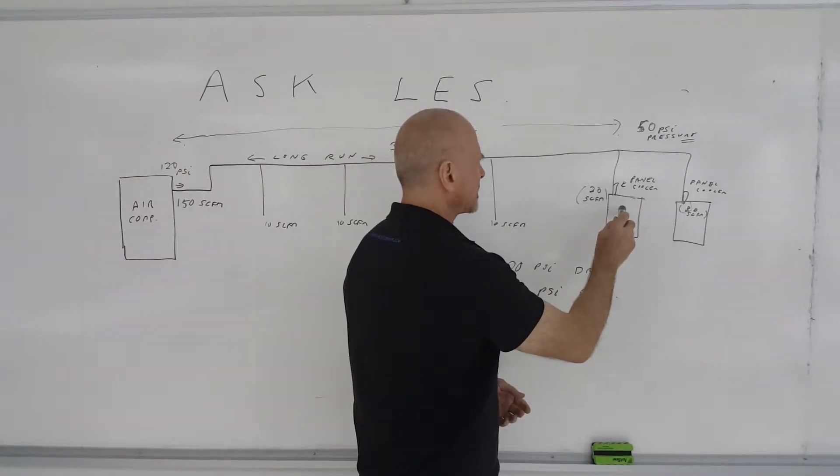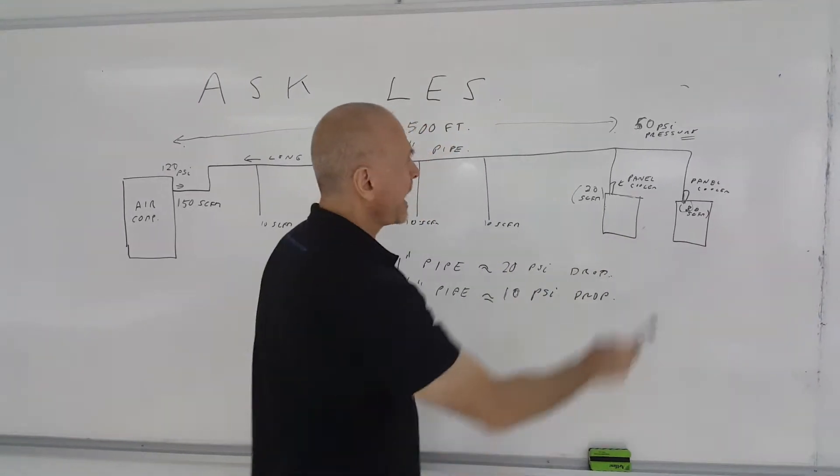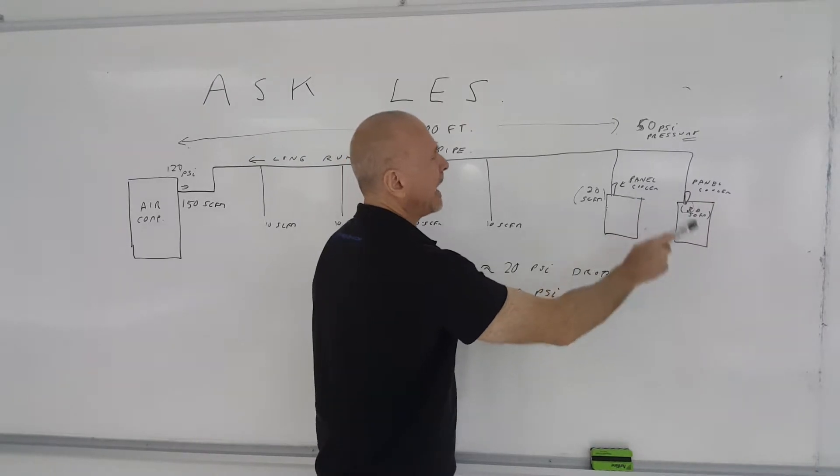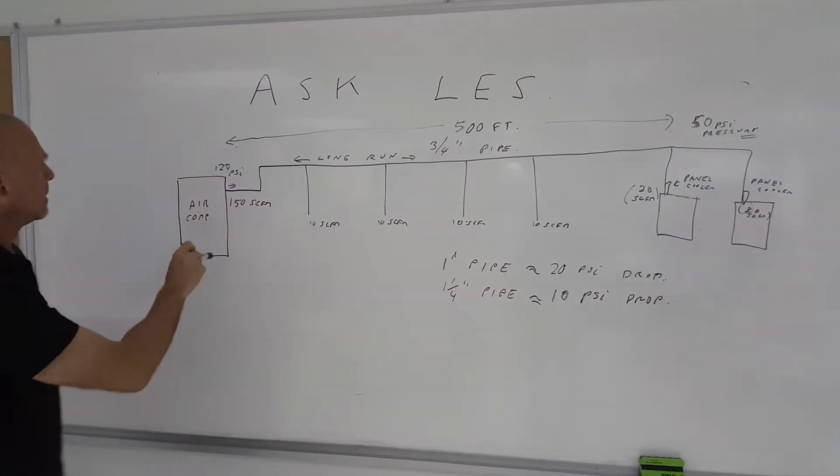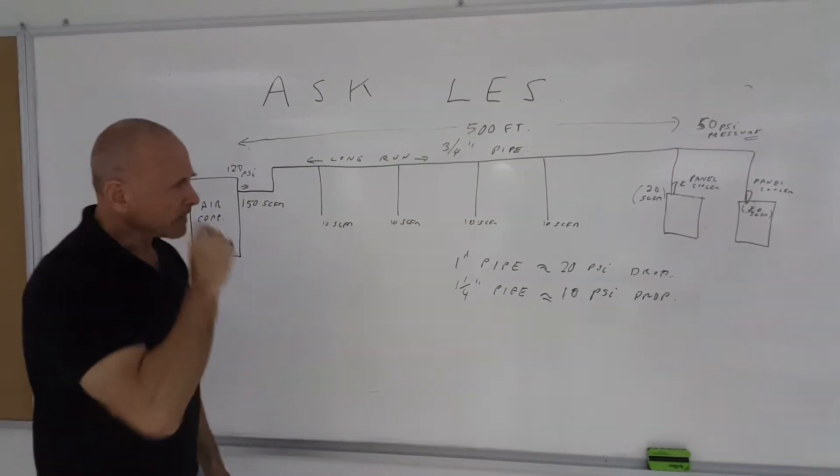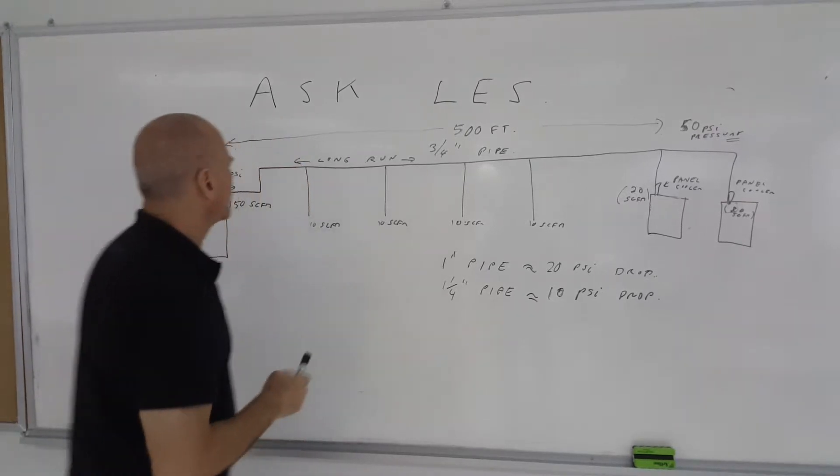So, they installed a 20 SCFM cooler on each of two control panels. However, the panel coolers were at the opposite end of the factory where the compressor was located. And they were having some problems. They weren't getting the pressure that they wanted going into the coolers. Why?